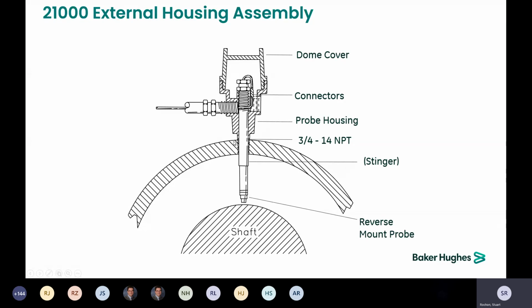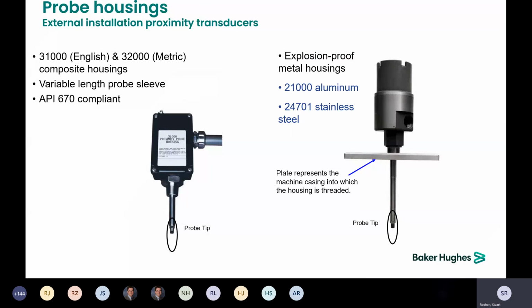And if we have the measurement from the outside of the machine case to the shaft, we can pre-cut and thread that stinger for you. Or if you want, we can supply you with a long stinger that can be cut and then internal threads tapped into the bottom of the stinger to mount the reverse mount probe. We offer 2 varieties or 2 styles. The 31,000, 32,000 is a composite housing. It is API 670 compliant. And then we have the explosion proof in a 21,000, which is aluminum, and the 24,701, which is a stainless steel.